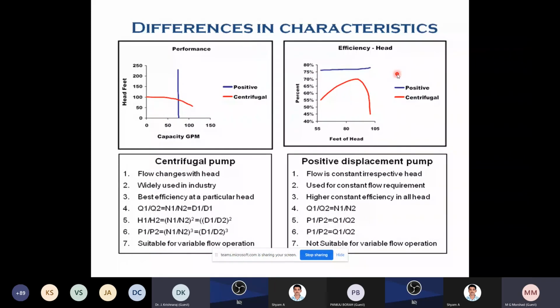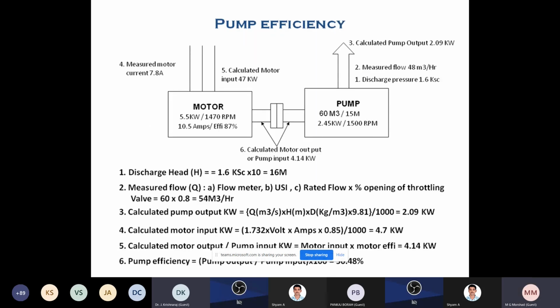So there is a distinct difference between the centrifugal pump and the positive displacement pump. And because VFD is a very costly matter, don't accept such a recommendation, and don't give such a recommendation. Try to give the right recommendation for the pump. Now, pump efficiency, I am not going to discuss this. It can also be calculated locally.